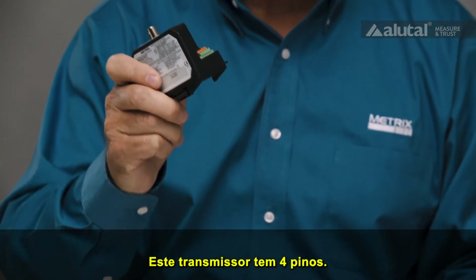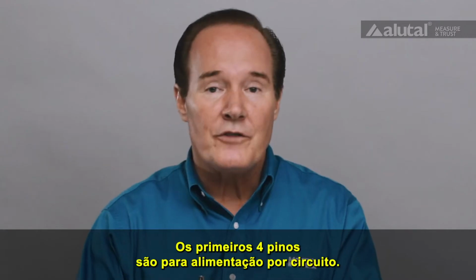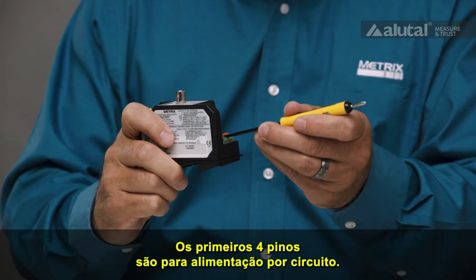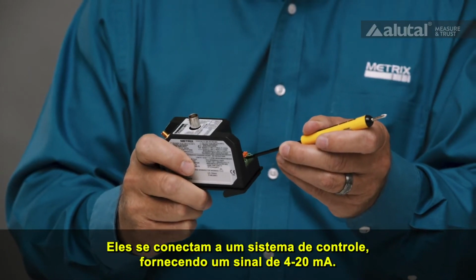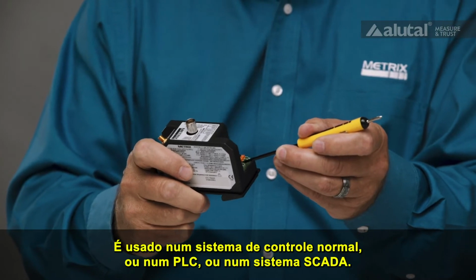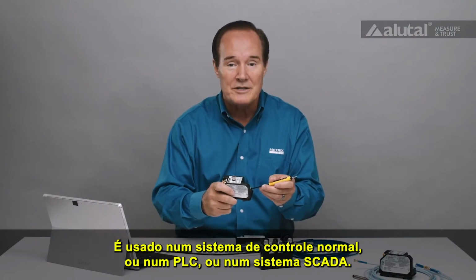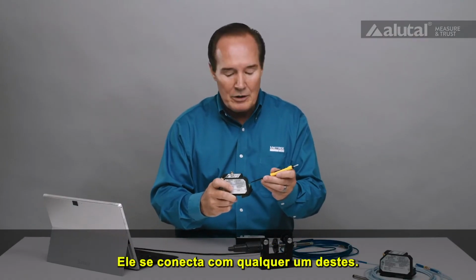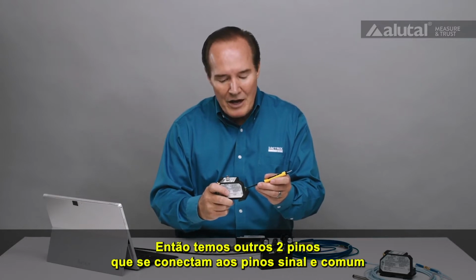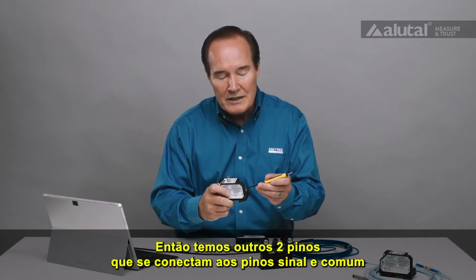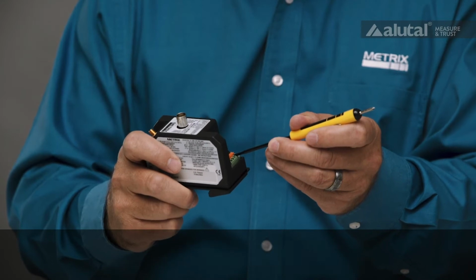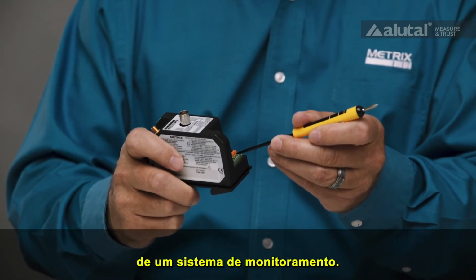This particular transmitter has 4 pins. The first 2 pins are for loop power, and that would go to a control system. That provides the 4 to 20. That would go to your normal control system or to a PLC or a SCADA system. It would go to any one of those. And then we have another 2 pins that go directly to the signal and common pins of a monitoring system.